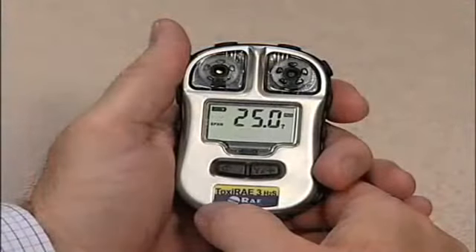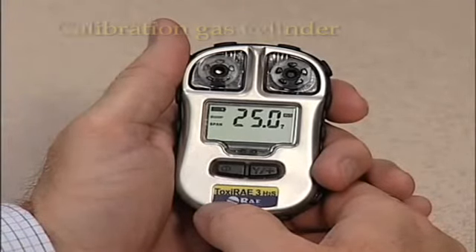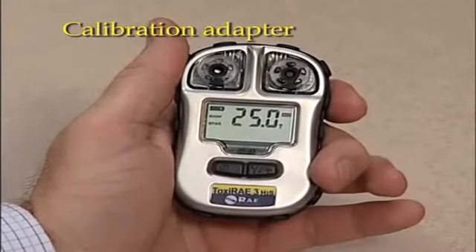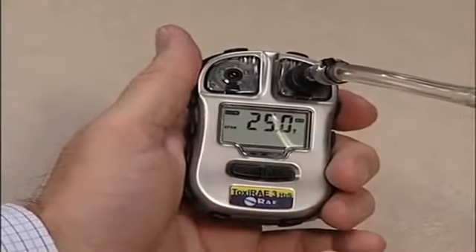Check that the bump gas concentration is the same as the gas cylinder's concentration. Connect the calibration gas cylinder, flow regulator, and calibration adapter to the ToxiRAE 3 and start the gas flow.